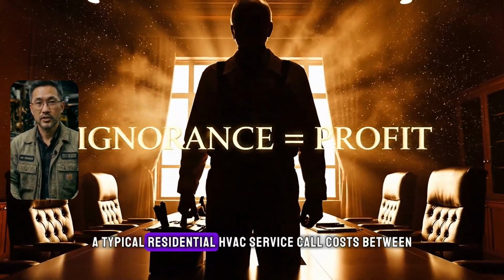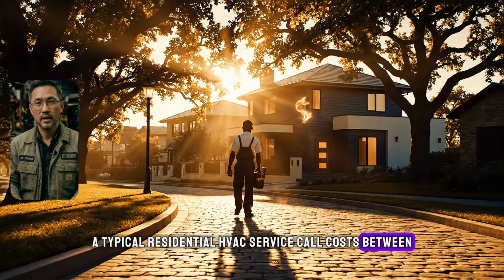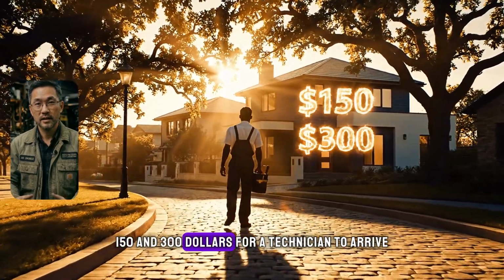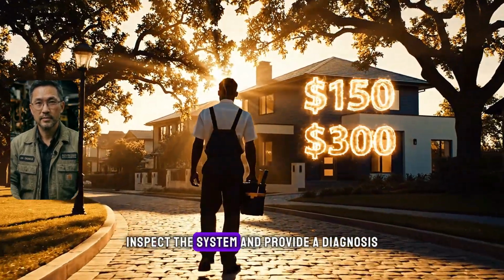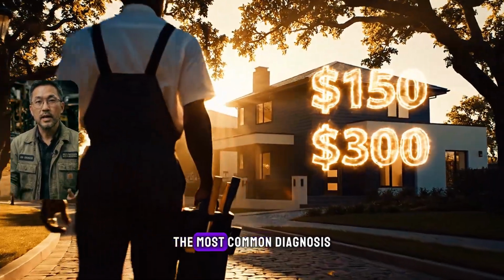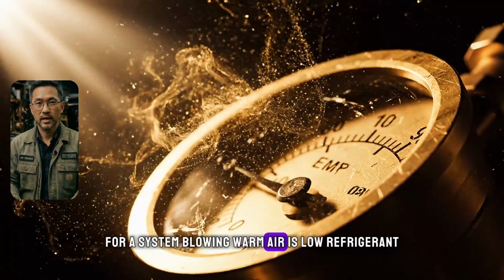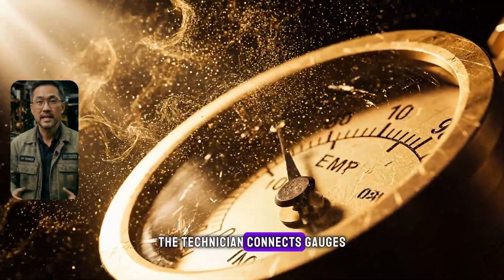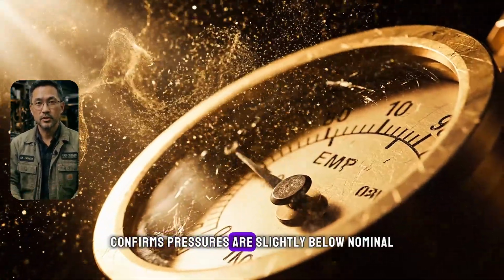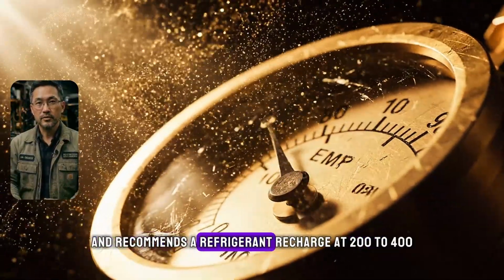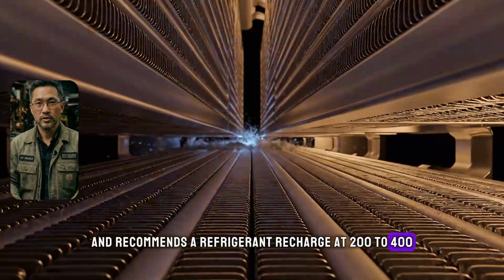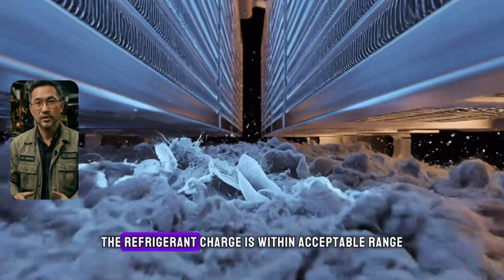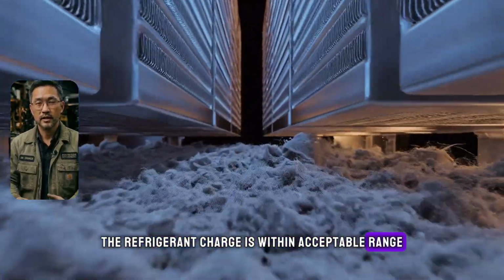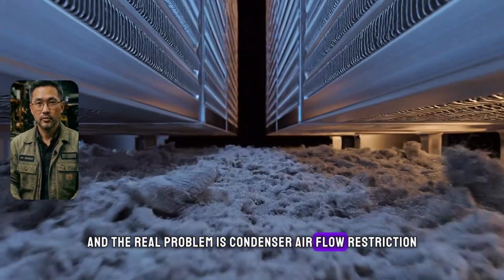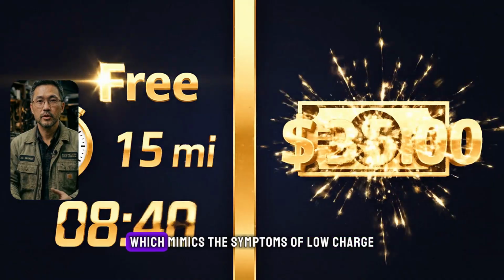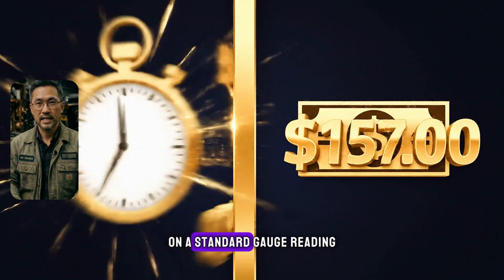The typical residential HVAC service call costs between $150 and $300 for a technician to arrive, inspect the system, and provide a diagnosis. The most common diagnosis for a system blowing warm air is low refrigerant. The technician connects gauges, confirms pressures are slightly below nominal, and recommends a refrigerant recharge at $200 to $400. In many cases, the refrigerant charge is within acceptable range, and the real problem is condenser airflow restriction causing elevated head pressure, which mimics the symptoms of low charge on a standard gauge reading.